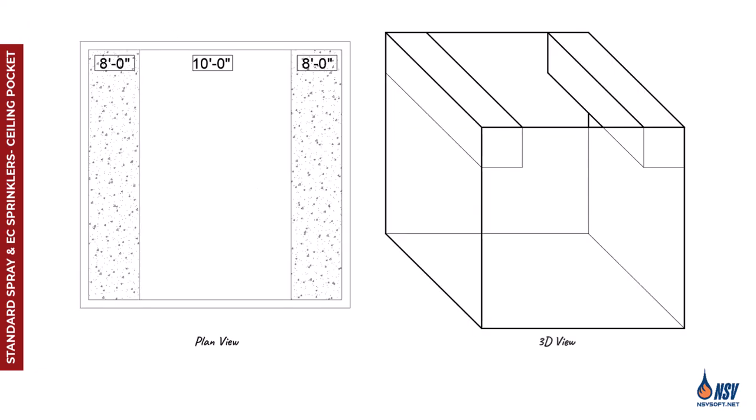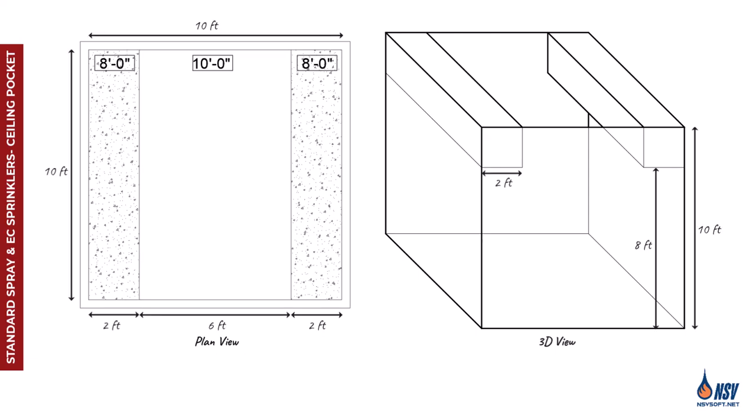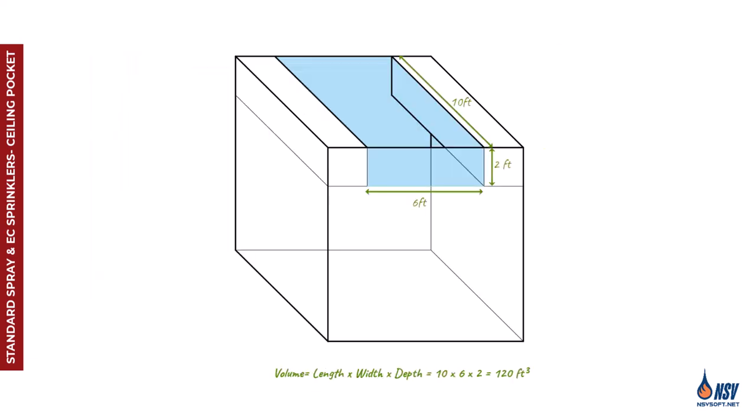For example, in the square-shaped room shown in this figure, let's assume the ceiling pocket has non-combustible finishes. The depth of the pocket can be calculated by subtracting the soffit height from the ceiling height, which gives us 2 feet. Then, by multiplying the length, width, and depth, we find the total pocket volume is 120 cubic feet.